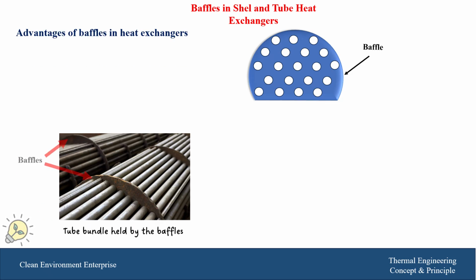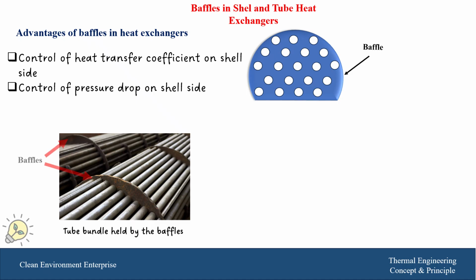And the advantages of the existence of these baffles in heat exchangers: they control the heat transfer coefficient on the shell side and control the pressure drop as well on the shell side.